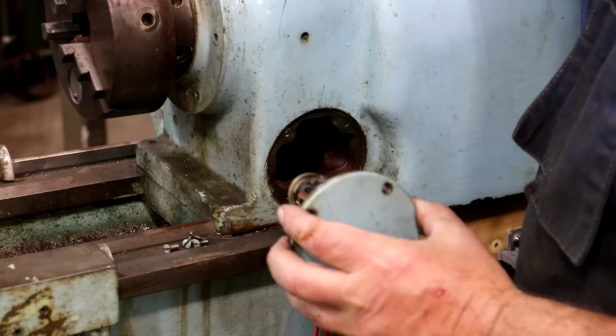If you look, there's a jumper between those two, and that's going to reverse. It'll connect wires 35 and 36. When you go forward, 37 and 38 connect. There's one more here that, when in the off position, connects those wires, but we're not using those in this setup. They're there if we needed them.